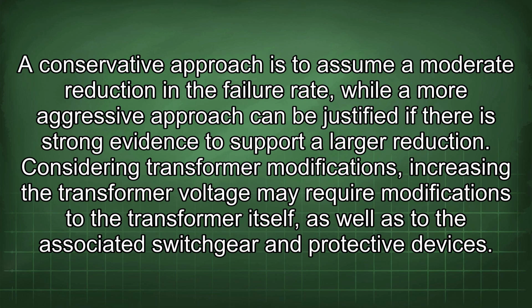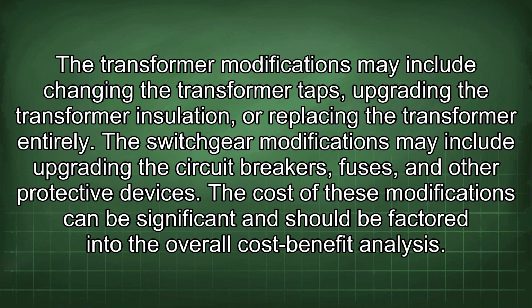Considering transformer modifications, increasing the transformer voltage may require modifications to the transformer itself, as well as to the associated switchgear and protective devices. The transformer modifications may include changing the transformer taps, upgrading the transformer insulation, or replacing the transformer entirely. The switchgear modifications may include upgrading the circuit breakers, fuses, and other protective devices. The costs of these modifications can be significant and should be factored into the overall cost-benefit analysis.